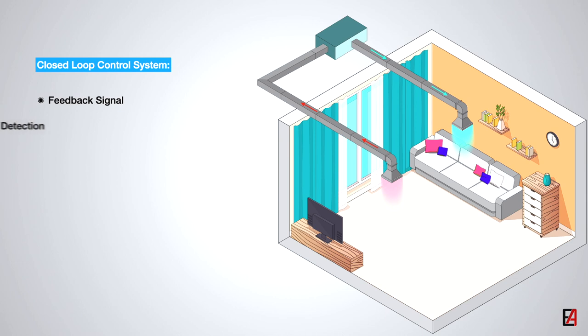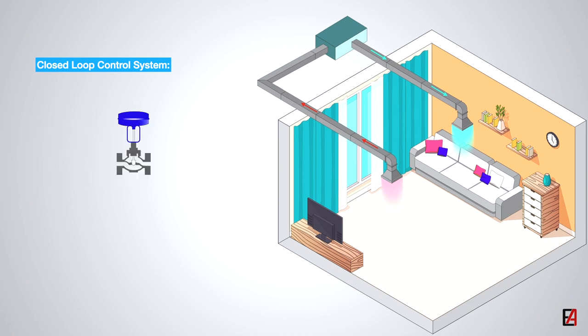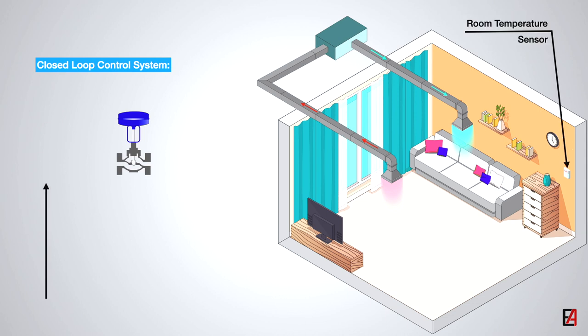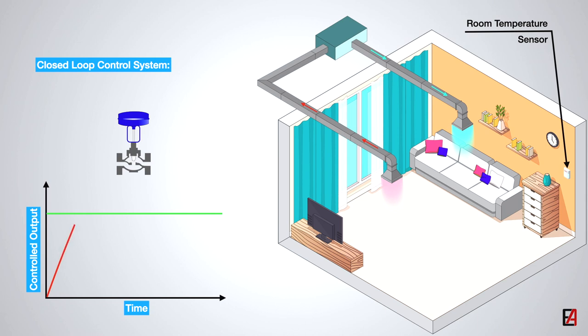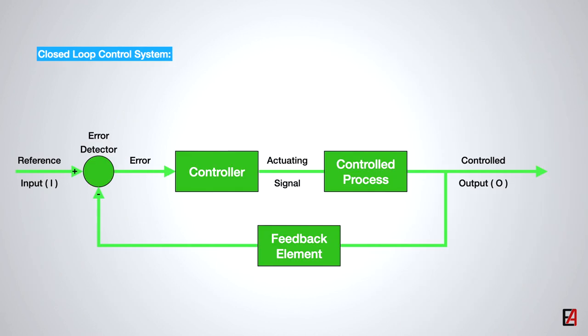A control system with one or more feedback paths is called the closed loop control system or feedback control system. Using the same example of maintaining room temperature, a room temperature sensor is provided as feedback to the controller to calculate the error between the desired temperature and the actual room temperature. Now the controller can decide how much the chilled water control valve needs to be opened to maintain the desired room temperature, and will actuate the control valve to eliminate the error. As the controller gets real-time feedback of the room temperature, accurate and stable control can be achieved.